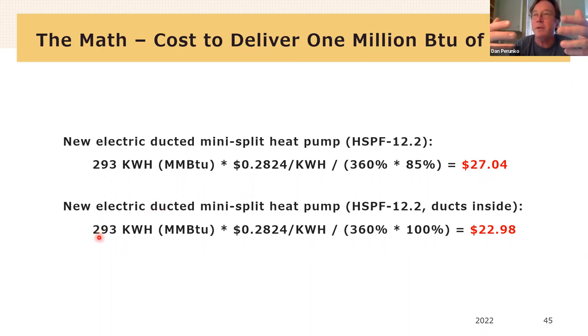There's this other thing that we can do, especially with heat pumps, and I'll explain why later. It has to do with the physical size of the equipment itself, which is move the system from like the attic or the crawl space into the inside of the building enclosure. And when we do that, our thermal losses go away, right?